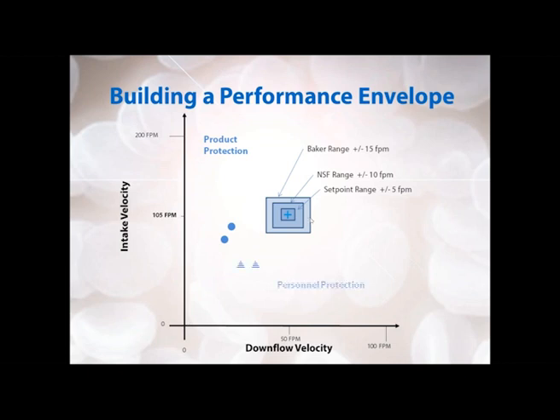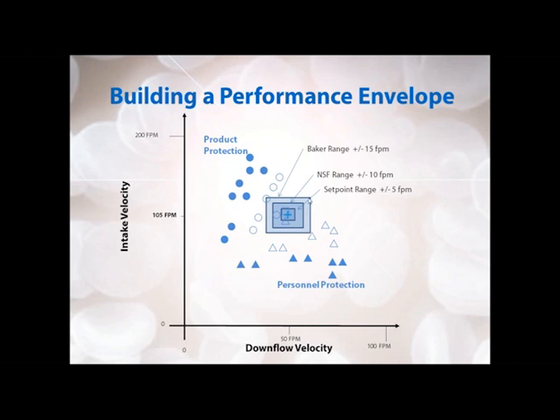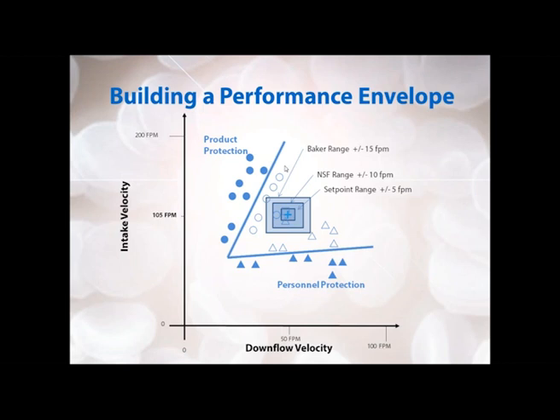Going back to the performance envelope we're building — showing the set point and all the different ranges required for testing, including the set point range, the NSF range, and the Baker range — we can start to plot our test results for product protection and personnel protection. We perform a lot of tests to gather sufficient data showing where failures and passes occur. We also test outside the required ranges just to see how far the cabinet can go. We do want to see some failures, because at the juxtaposition of passing and failing, we can draw lines that tell us where the cabinet's restrictions are — how far out it can go before failing. These lines are your performance envelope.